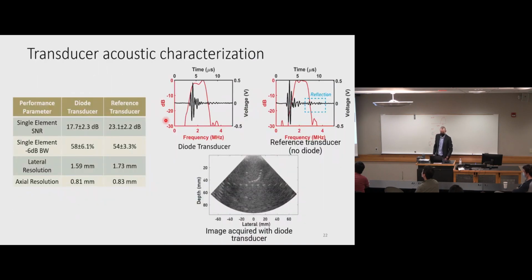So how well does this thing work acoustically? Well, we definitely don't have the really broad bandwidth of Dr. Olkan-Siemats here, but we do have an okay bandwidth for cardiac imaging. So on the left here is our acoustic diode transducer, and you can see that it has a slightly lower signal-to-noise ratio than this particular reference transducer. We have a few different control or reference transducers that we built to compare it with. In this case, what I'm comparing it with, which is this plot on the right, is a transducer that has the same thickness, but without those air-filled voids, without that acoustic diode in there.